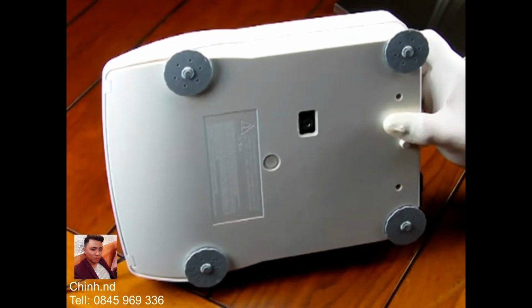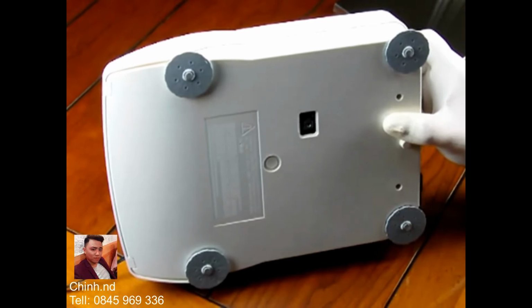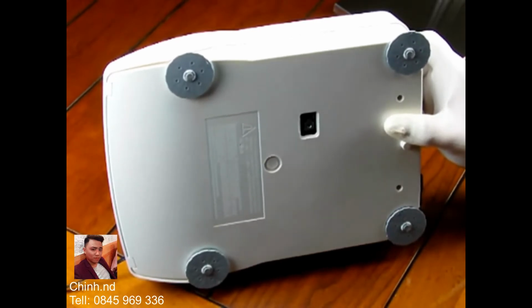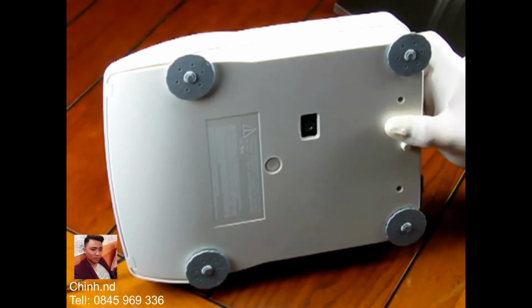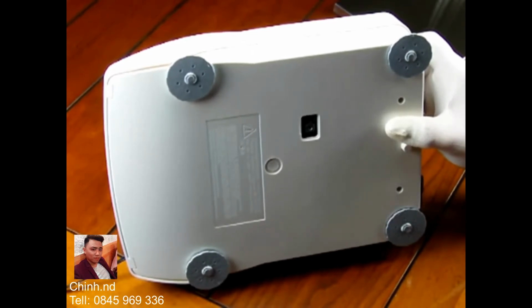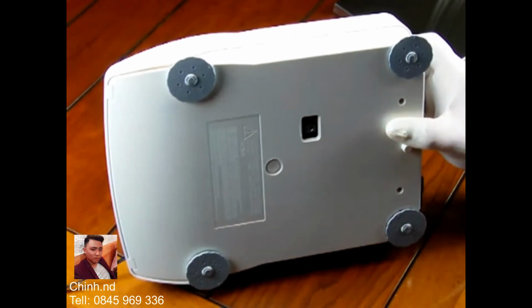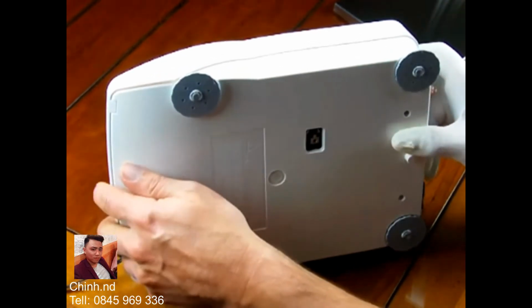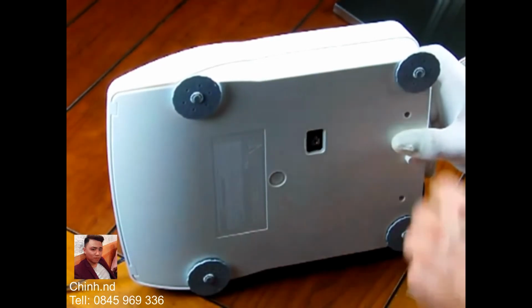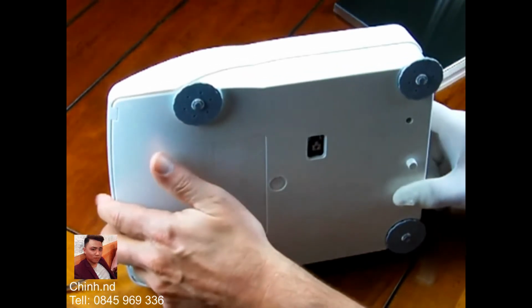A lot of balances on the market, they don't offer an underhook. And this is something that's really used if you're ever doing any kind of specific gravity density determination. You would suspend a wire from here and put your sample, we'll say, in water. Sometimes they use alcohol or glycerin. So again, we have 4 adjustable feet for easy leveling.